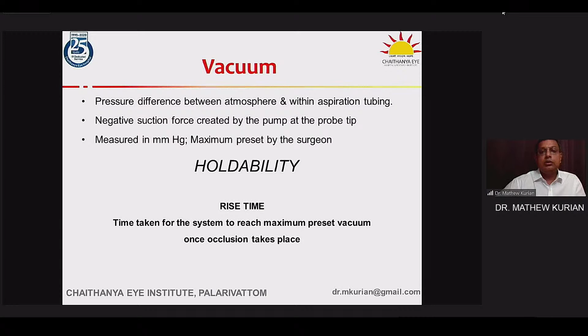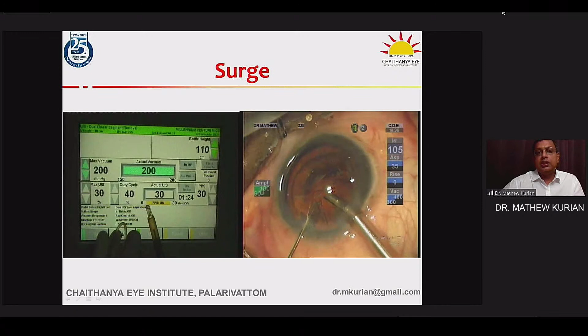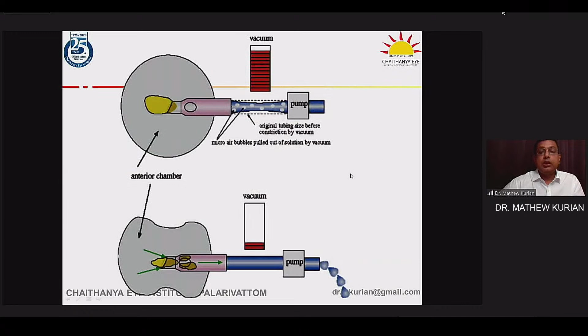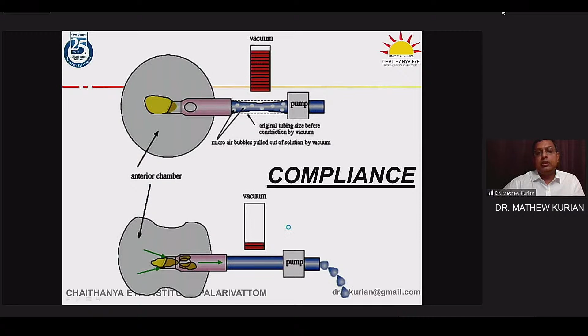Chamber stability is something, the small flickers as it happens, that is basically a surge happening which is not related to a complication. In other situations, it could cause a PC event. What can we do to eliminate or reduce surge? It is to go with the compliance of the tubings. A more compliant tubing tends to collapse and is associated with the likelihood of surge. A low compliant tubing remains rigid even when the vacuum buildup happens. As a surgeon, we can reduce the outflow by using low aspiration rates, decreasing the aspiration port size. We can attempt to increase the inflow by raising the bottle height, but be sure that you don't do it at the expense of turbulence.